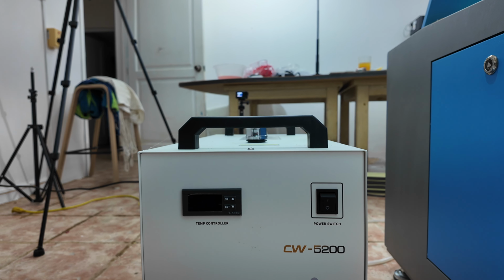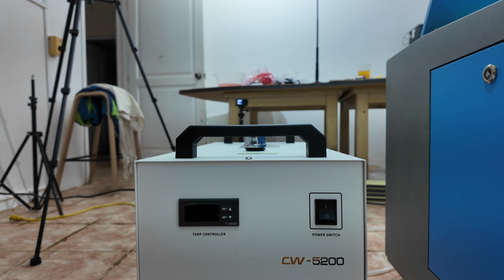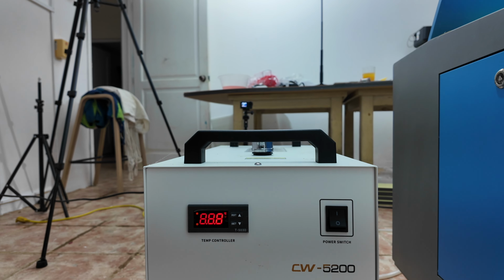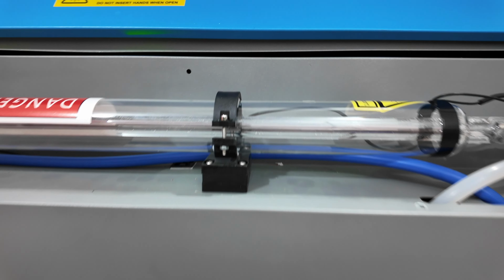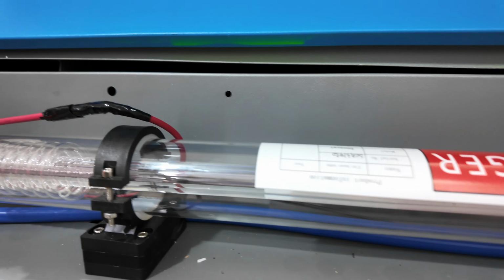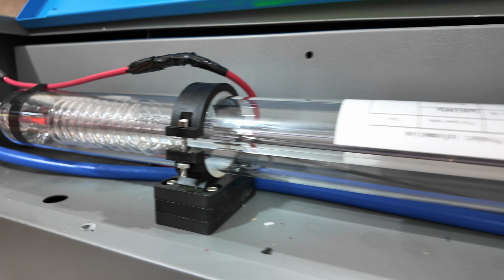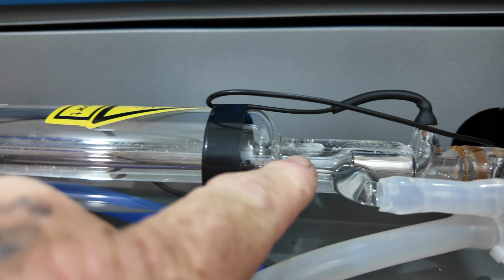So now that we have the chiller connected, we're going to go ahead and check the water levels, power the water chiller up, make sure that the water bleeds through, and go ahead and bleed the laser again before we power it up. So coming on down to the front of our water chiller, we are going to power the water chiller up, and we can hear the water pumping. And we come over here and we are now watching for any air bubbles. There we can still see a few air bubbles.